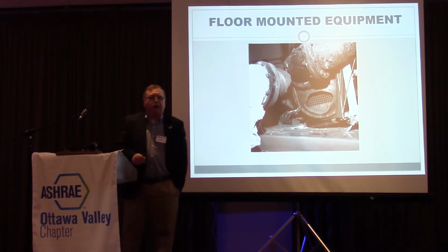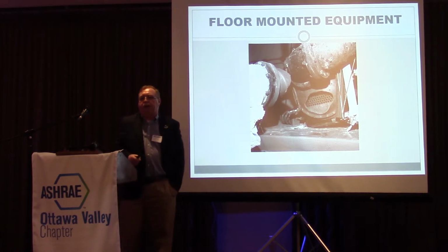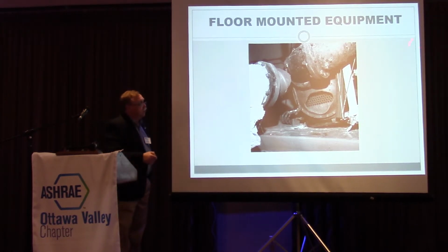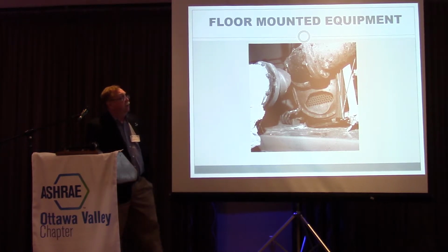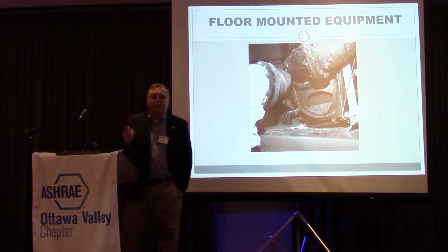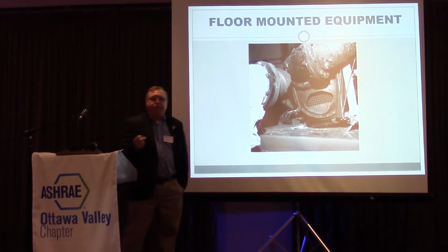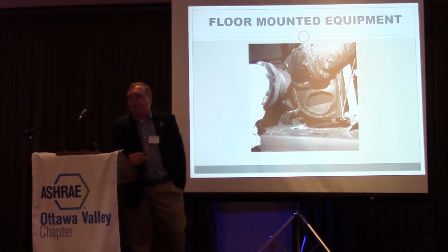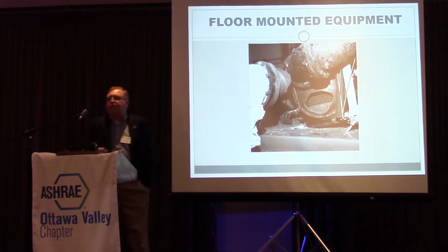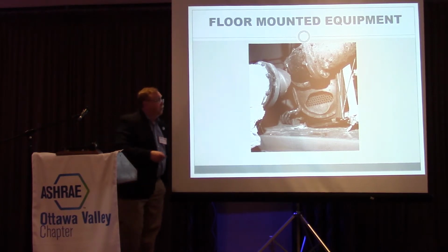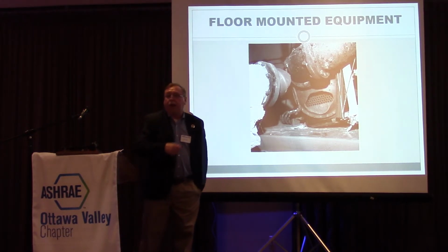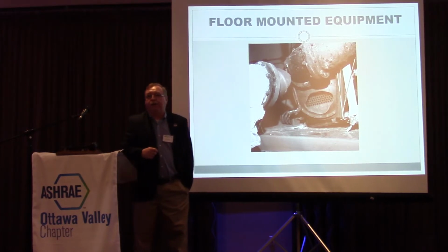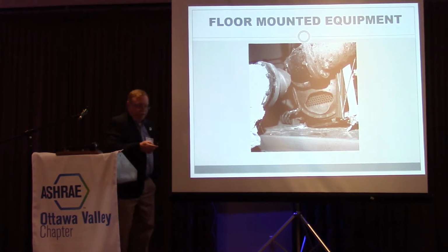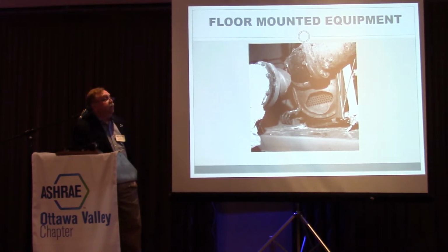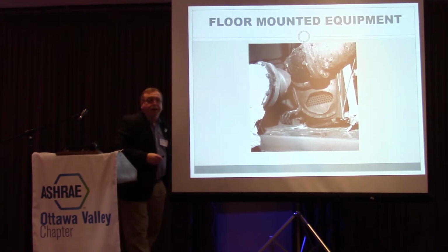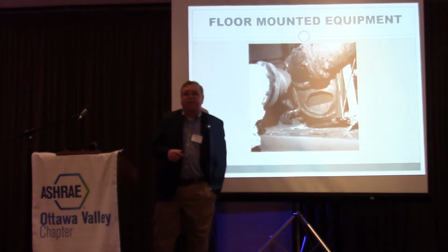But what if you're a hospital and you need that? The thing to do is put a flex connector in here. One of two things will happen: the flex connector will move enough so that nothing happens during the earthquake, or the flex connector fails, and then you put a spool piece in the next day, and the hospital's up and running again. That's all you need to do. Flex connectors can be a godsend, and they can also be your biggest enemy.